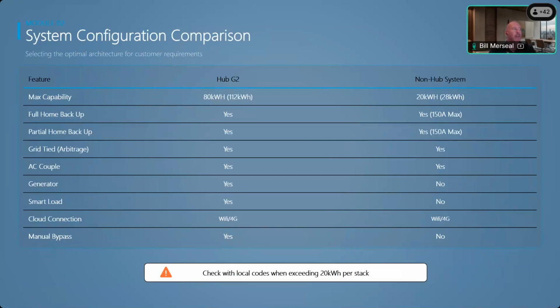So one thing that we talk about with local codes is that the reason we put this in there is because in the United States, there's an NFPA rule that says we can only have up to 20 kilowatt hours per stack inside, right? So depending on certain circumstances, if there's a firewall or anything like that, we can go up to 28. Some locations are more strict than others.